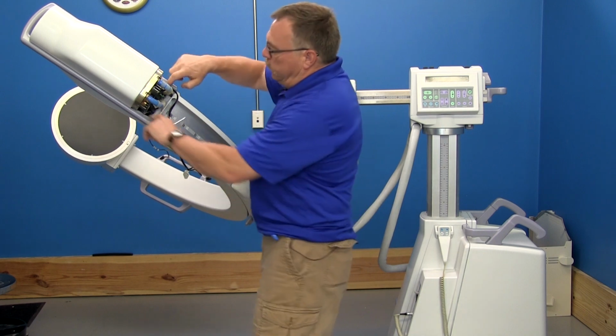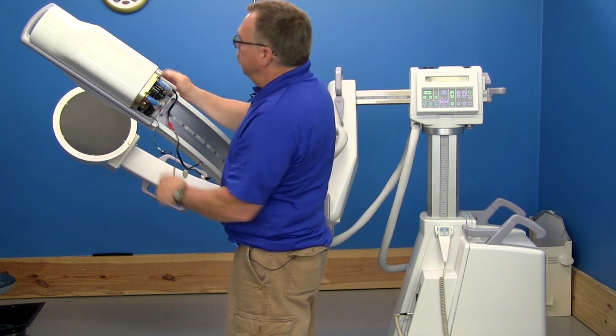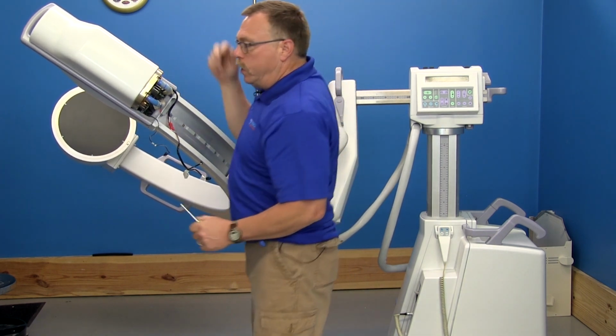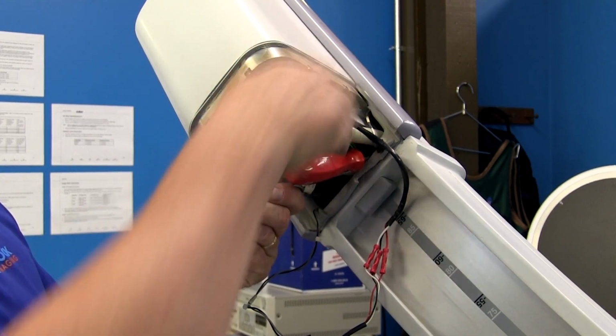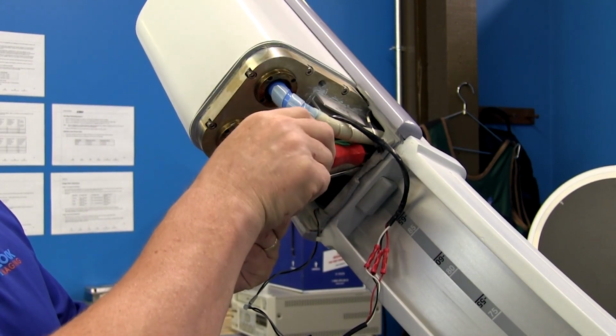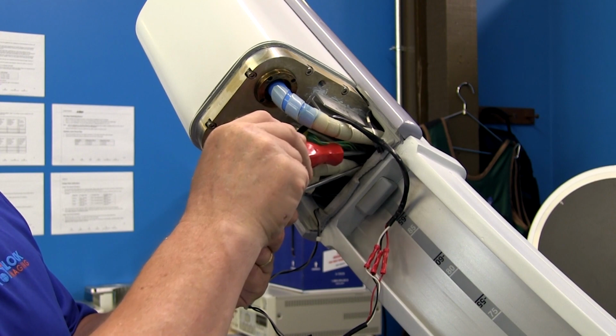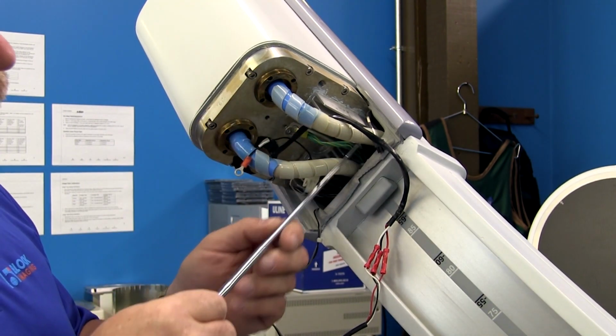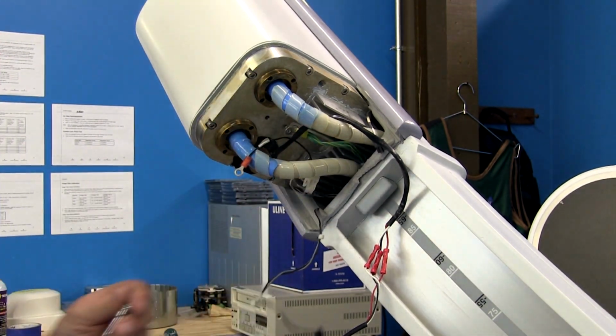You've got a ground strap here that's screwed into the tube itself that needs to come off. Now we have two screws down in here that hold this top cover on. This is where you want to make sure you have a magnet available, because when you unscrew the screws, you don't want them to fall down inside the C. So I usually put my magnet up here so I can catch them as they come out.